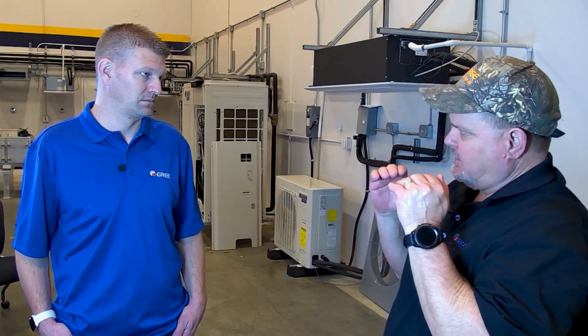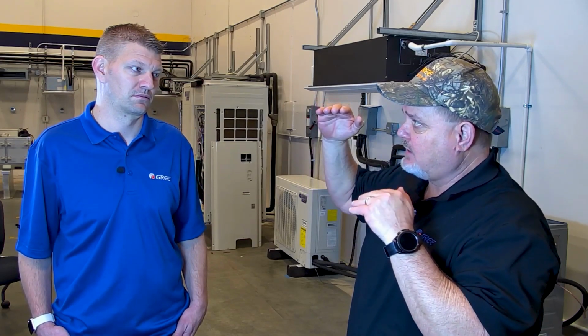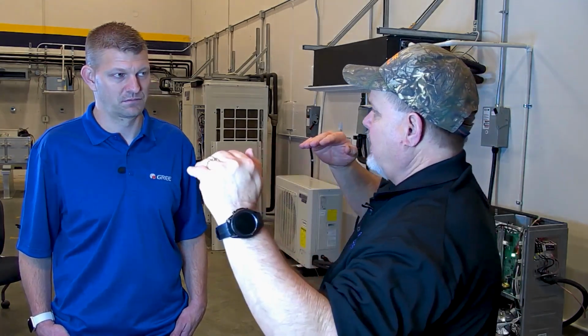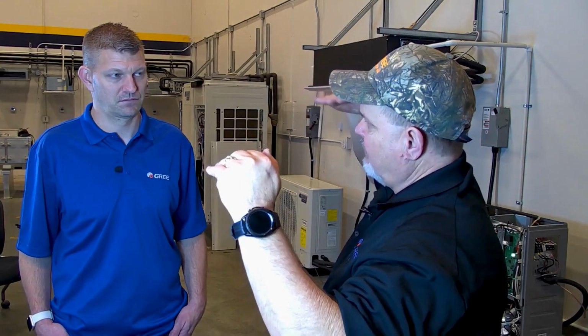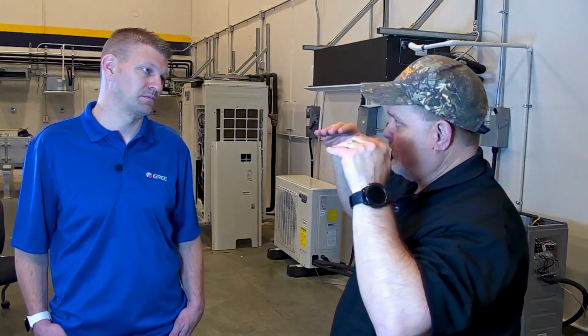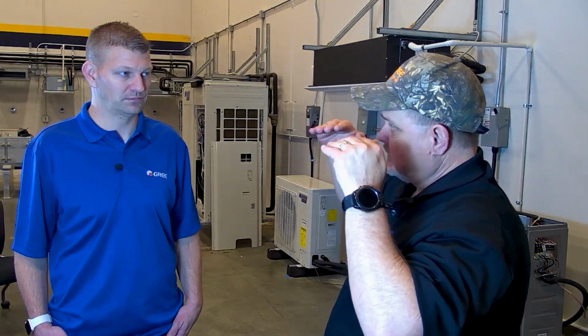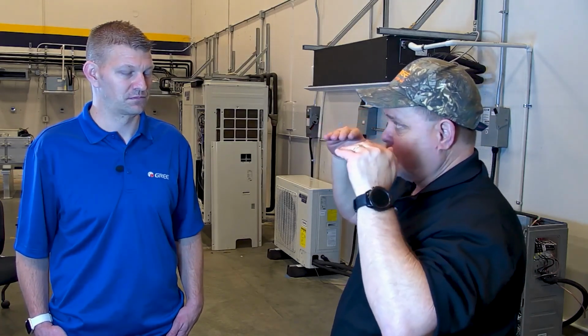So if you're zoning, what you're doing is you're turning the temperature down in the zone you're not calling for, right? But then you're coming back and possibly putting a high demand on that. That's not ideal with an inverter-driven system, because now you're forcing that outdoor unit to ramp up to meet the level of demand, right? Right. Efficiency-wise, you'd be better off leaving that zone within a couple of degrees, right? And keep all the zones within a couple of degrees and let that heat pump maintain temperature at those lower revs. See what I'm saying?